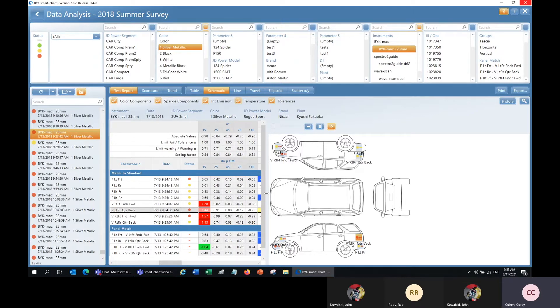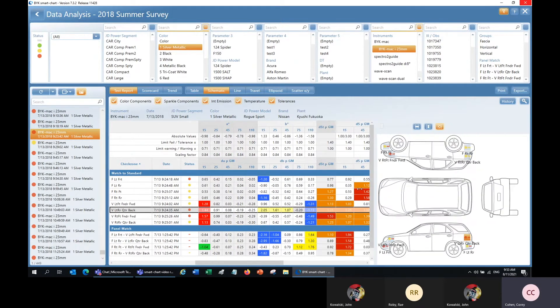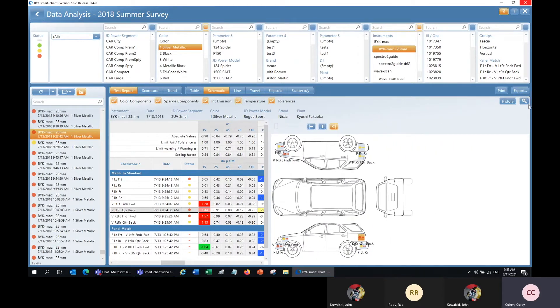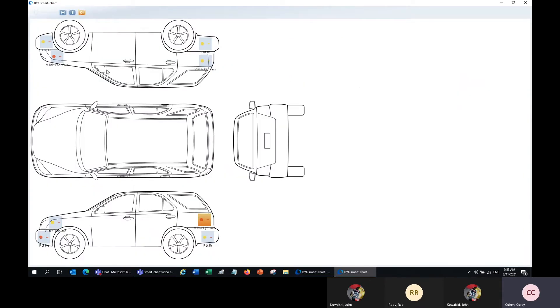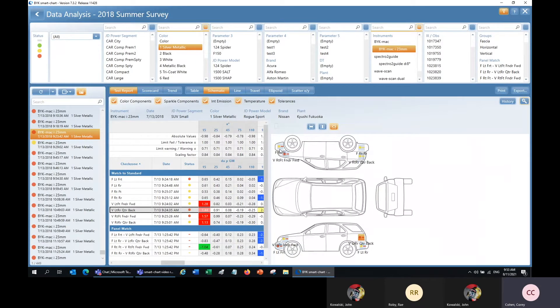If you don't like the view, you can move this back and forth to view more or less data. You can also click the plus sign magnifying glass button in the corner to bring it up to its own window. In each check zone, you'll see small dots — the larger single dot indicates the traffic light condition of the match to the standard, determined by the tolerances. The double dots indicate the panel match status, whether it's red for out of tolerance or yellow for in tolerance but close to the edge.